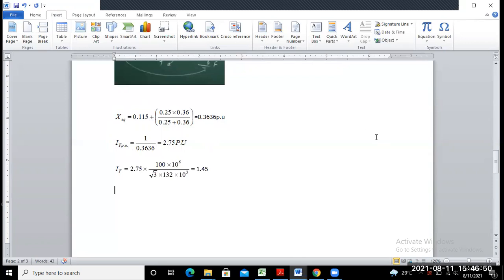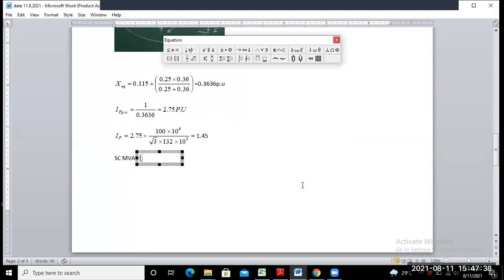So the pre-fault voltage, you consider as 1 at an angle of 0 degree, and the fault current you have already found here in per unit. So just simply multiply 1 into this one. That means short circuit MVA in per unit, is it not? So simply, short circuit MVA is equal to pre-fault voltage value into fault current. That means the fault current is this one, and the pre-fault voltage value is 1 at an angle of 0 degree. So just simply multiply this one by 1 into fault current. So what is the value of the fault current? 2.75.